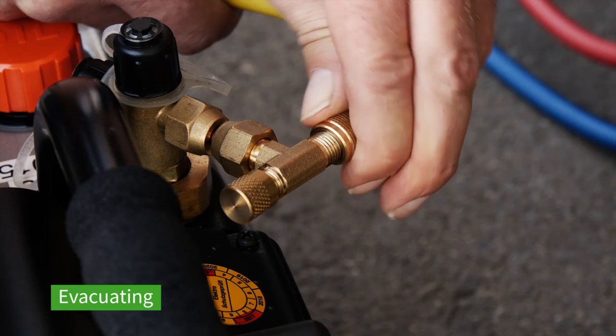Evacuate the entire pipework to a pressure of at least 1.5 millibars using a suitable vacuum pump.